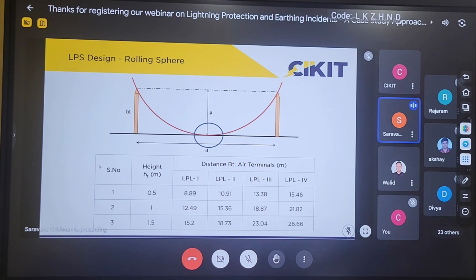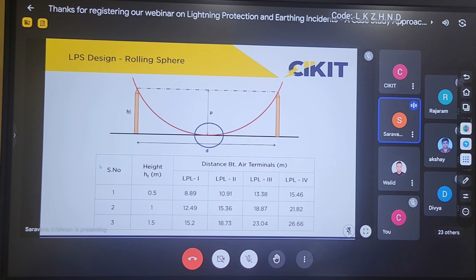If I am going for the rolling sphere method, here also it is not mandatory that I have to go for a 1 meter air terminal. Based upon the site conditions and the design, I can decide whether to go for 1 meter, 2 meters or 3 meters. If I go for a 3 meter air terminal, then the distance between the air terminals will be much higher and the number of air terminals will be very much reduced. So it is up to the designer to decide whether to go for 0.5 meters, 1 meter or 1.5 meters.